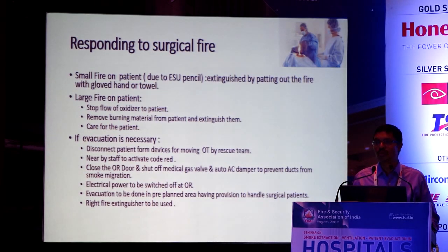Okay. The content has been basically taken from ECRI. For a small fire due to the electrosurgical unit pencil, extinguish it by patting the fire with a gloved hand or towel. If it is a large fire, stop the flow of the oxidizer to the patient. Remove the burning material from the patient and extinguish it.